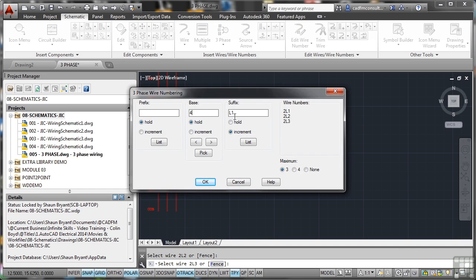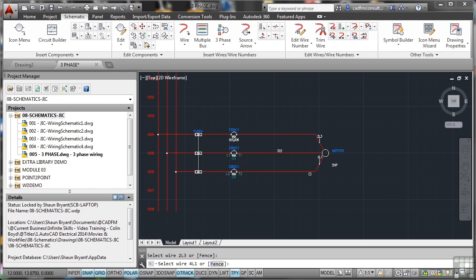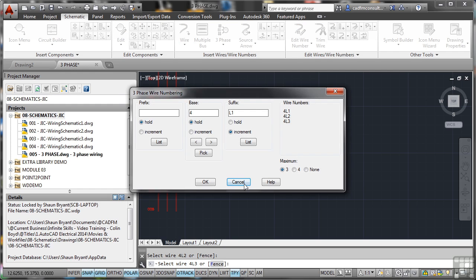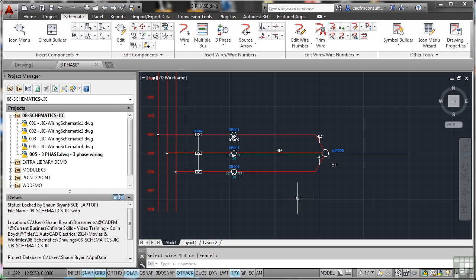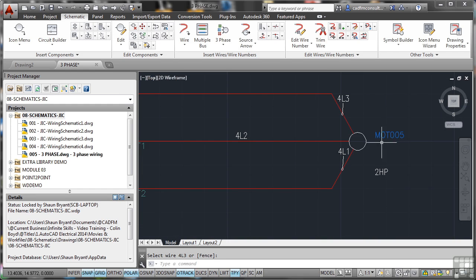If I click in there, notice the wire numbers update. When I click on OK, you'll see them update accordingly. So if I go 1, 2, and 3, you can see those update to 4, and then click on cancel — it's one of the only commands in AutoCAD Electrical where you click cancel or hit escape to come out. So there's our motor in there, 2 HP, with 4L3, 4L2, 4L1 as our wire numbering in place.